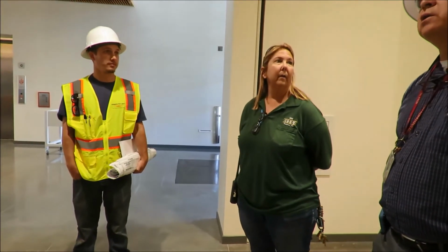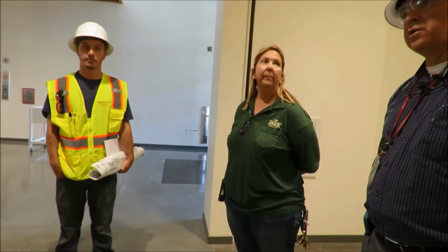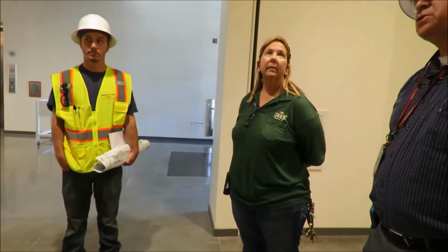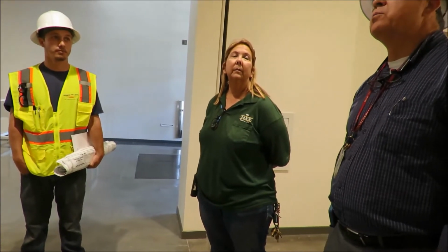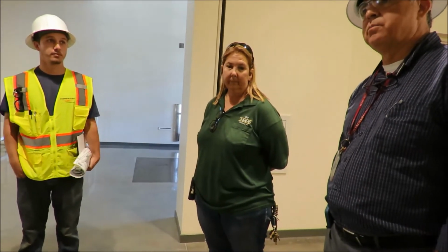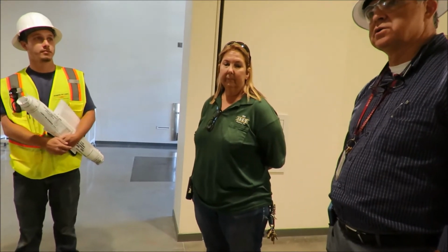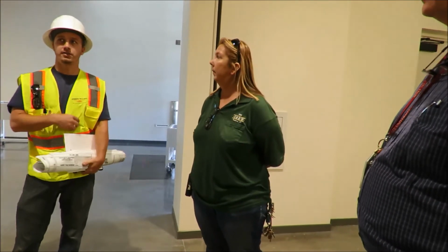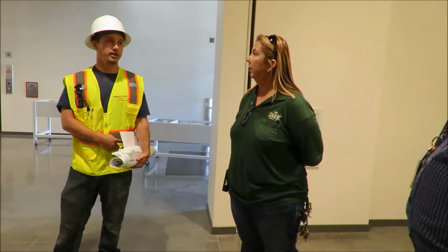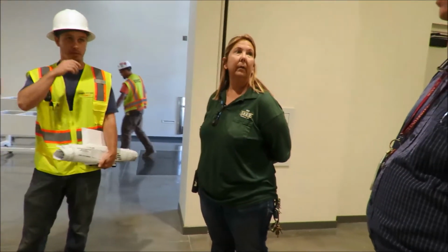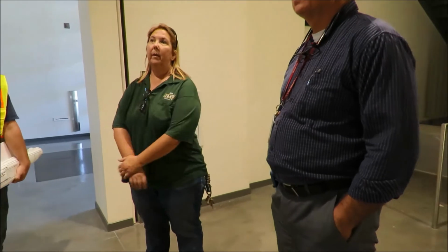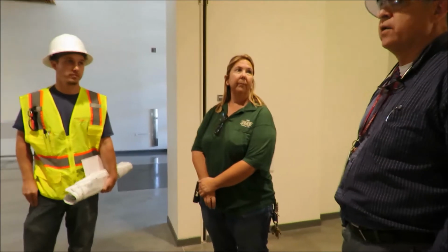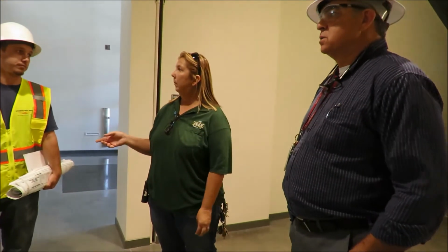Right now they're on regular power, and they're on all the time. It's all based on the Lutron. So they're controlled as normal lights, except for a power outage, and they're charged all the time. Even in a fire situation, I don't believe any of the lights shut off. They're completely separate, only for a power outage. They're egress lights and have nothing to do with fire or evac.